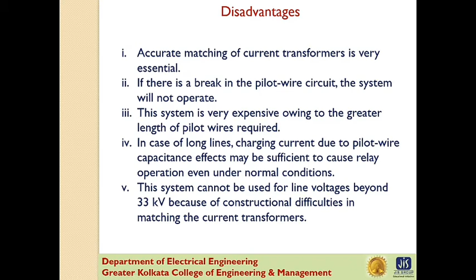What are the disadvantages? Accurate matching of current transformers is very essential. If there is a break in the pilot wire, the system will not operate. The system is very expensive owing to the greater length of the pilot wire cables. In case of a long line, the charging current due to pilot cable capacitance effect may be sufficient to cause relay operation under normal condition. Now this system cannot be used for line voltage beyond 33 kV because of the construction difficulties in matching the current transformers.